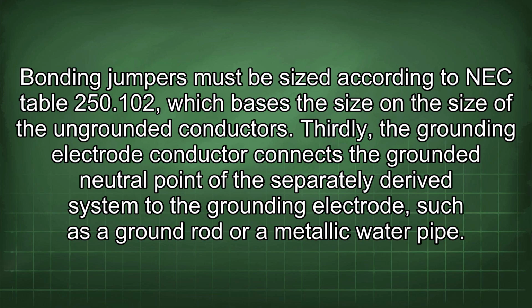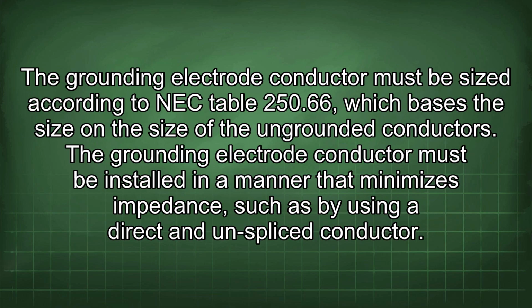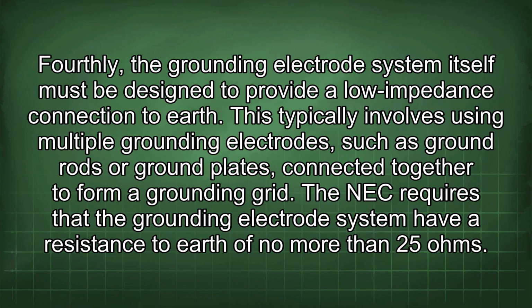Thirdly, the grounding electrode conductor connects the grounded neutral point of the separately derived system to the grounding electrode, such as a ground rod or a metallic water pipe. The grounding electrode conductor must be sized according to NEC Table 250.66, which bases the size on the size of the ungrounded conductors. The grounding electrode conductor must be installed in a manner that minimizes impedance, such as by using a direct and unspliced conductor. Fourthly, the grounding electrode system itself must be designed to provide a low impedance connection to earth.